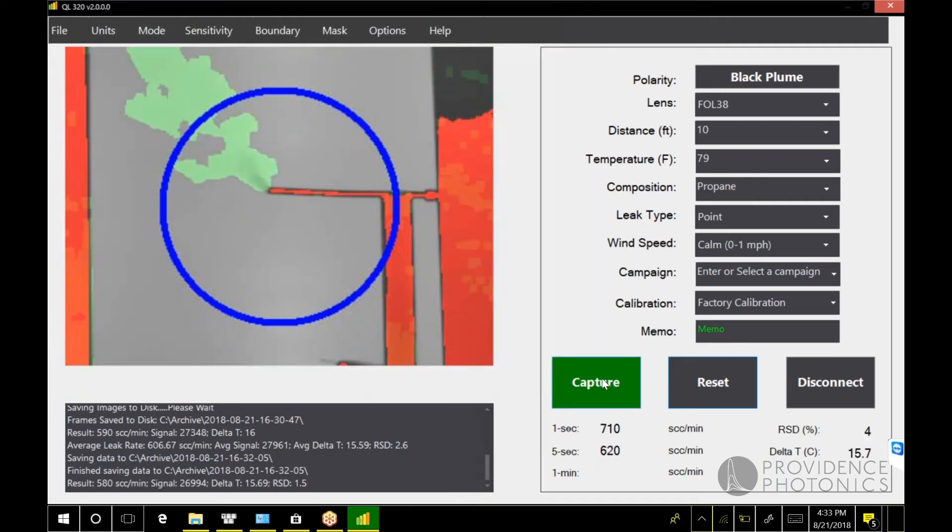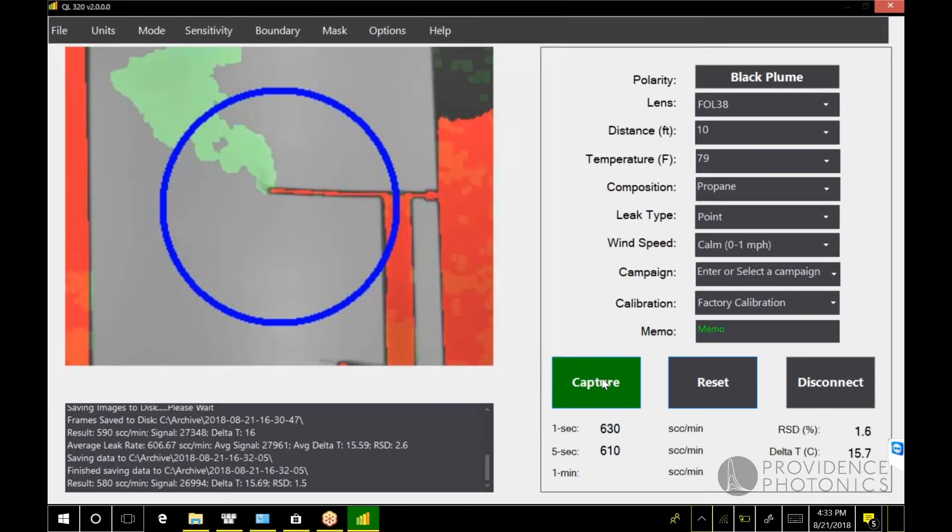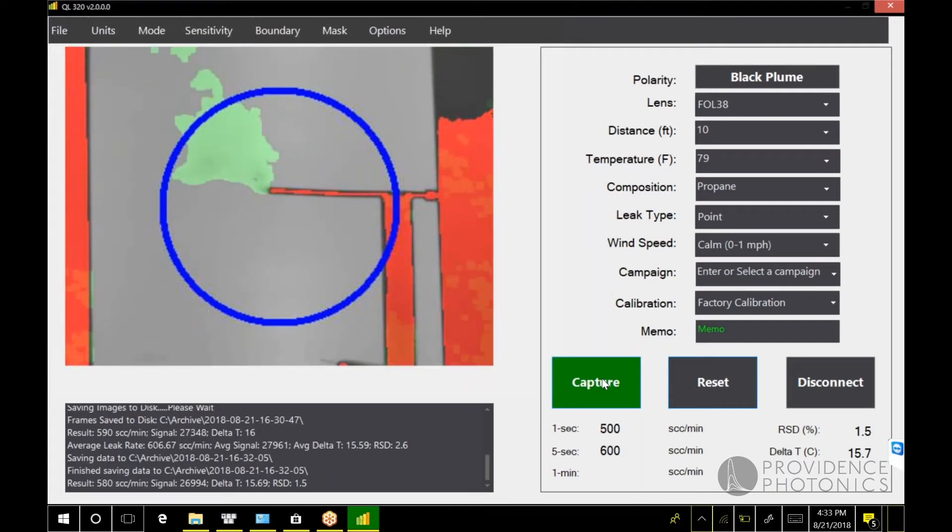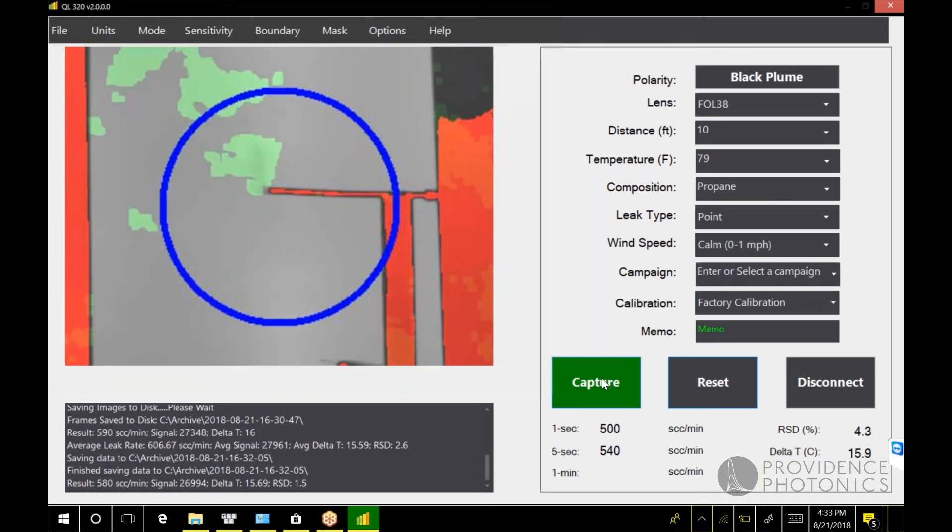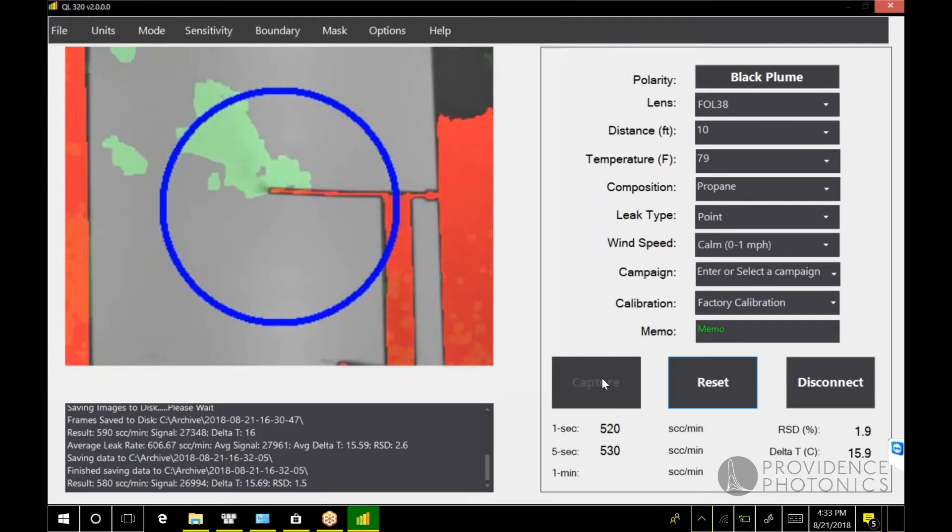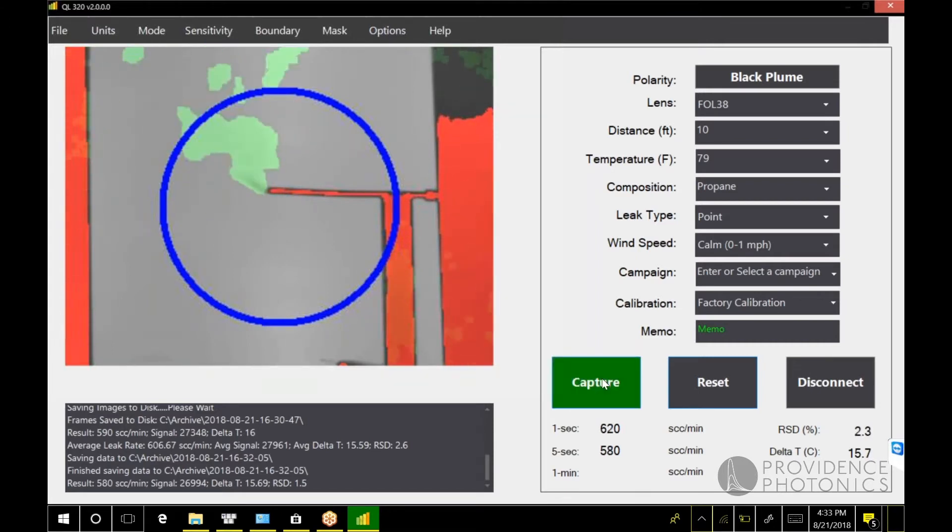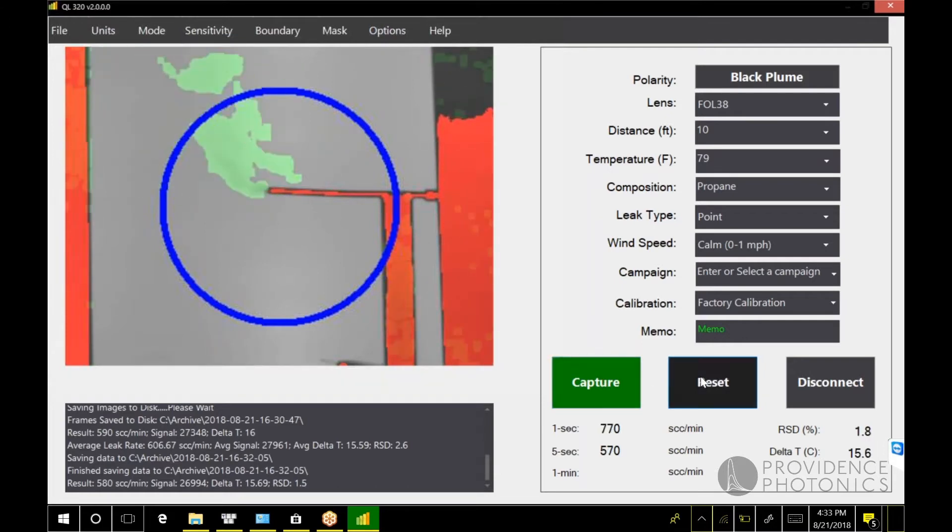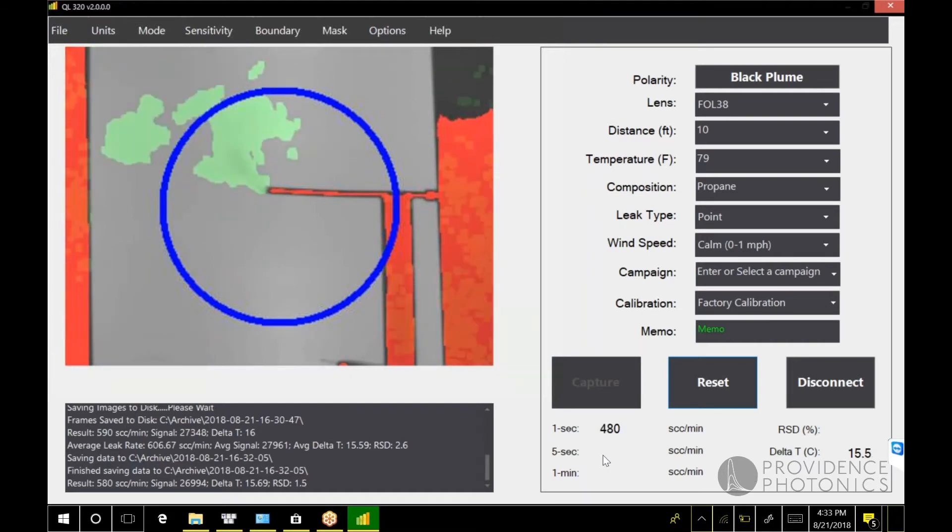Whenever the button's enabled, you can save the last five seconds of frames that derive this result. If it's green, it means your average values are close to each other, meaning your relative standard deviation is small and you have a good representative number. Basically the QL 320 is telling you it's safe to save this result now because you have enough data and the data is consistent. If you ever see the box go red, you can still save the results, but your averages may be further apart than you would like. Anytime you want, you can hit the reset button. It will reset the background or reset the averages and start counting again.